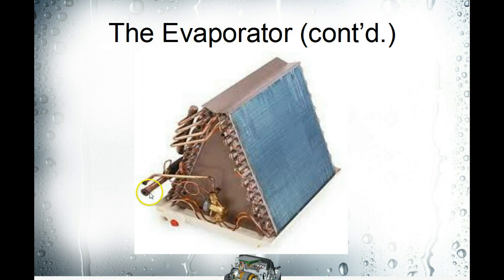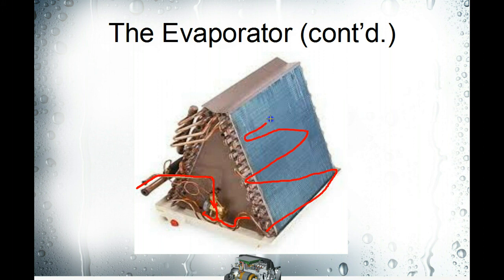Here's what an evaporator looks like. The refrigerant enters from the compressor through this pipe right here. This happens to be a TXV metering device, which we will go over in great detail. It drops the pressure at this point and enters the distributor, and the distributors feed that refrigerant through the evaporator coil. It flows back and forth through here through several different routes and exits right here, coming back out on the low pressure side of the system.